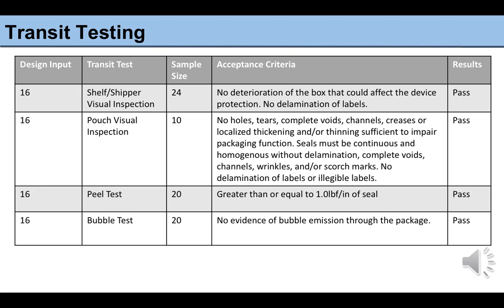The remainder of the protocol consisted of pouch visual inspection to identify any points of concern or weakness on the pouch contained within the shipper box, a pouch peel test, and a package bubble leak test, much like the packaging protocol, which we tested for the strength needed to pull apart the pouch in the Instron 5544, where we needed to exhibit a minimum tensile force of 1 pound. For the package bubble leak test, we fully submerged the package and wanted to ensure that there was no evidence of bubble emission through the package. All of these tests passed.